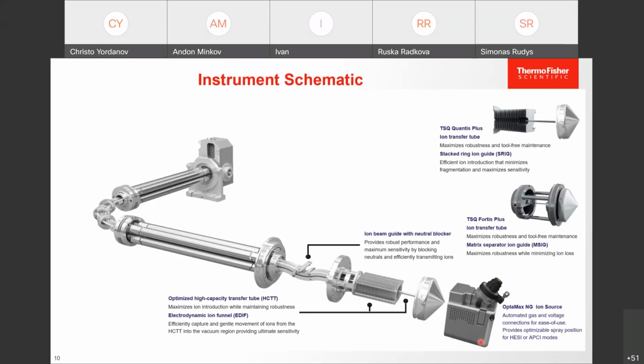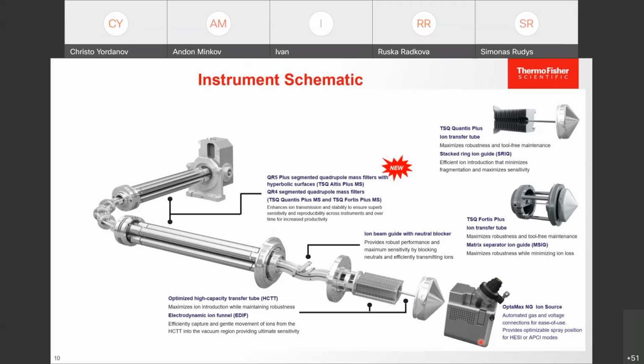After ion optics, we have an ion beam guide, which prevents neutrals from entering the quadrupoles, so it reduces noise and improves detection limits. The heart of the mass spec is, of course, the quadrupoles. The hyperbolic surface quadrupole is unique and the heart of the TSQ platform, which allows highly selective SRM at 0.4 or 0.2 Dalton quadrupole resolution, which prevents matrix interferences in the spectrum and allows lower detection limits.